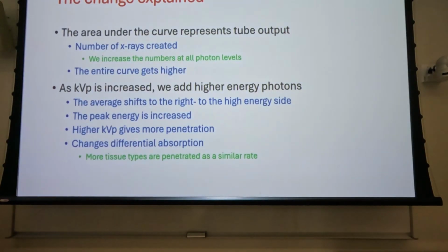All right, so the area under the curve represents tube output. That's the number of X-rays that we create. So it increases all of the numbers at all photon levels, and that's going to be important when we get into patient dose. The entire curve gets higher. That, again, represents our numbers. As kVp is increased, we add not just more, but higher energy X-ray photons.